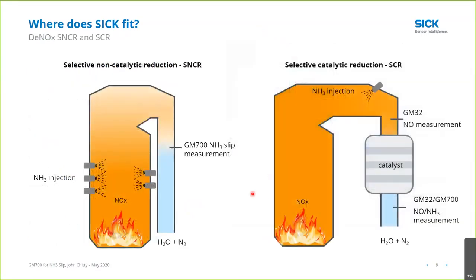Now, there are 2 types of reactors. There's an SNCR, which is selective non-catalytic reduction. In these, we inject ammonia into the flue gas, but there's no catalyst bed. So all we have to do here is measure the ammonia slip. On SCR, we do have the catalyst bed, so we inject ammonia, and we can measure the NOx going in and provide that feed-forward signal to the control scheme. And then on the outlet, we would measure ammonia slip, and potentially you could measure NO again there, or that could be measured on your CEMS system as well.